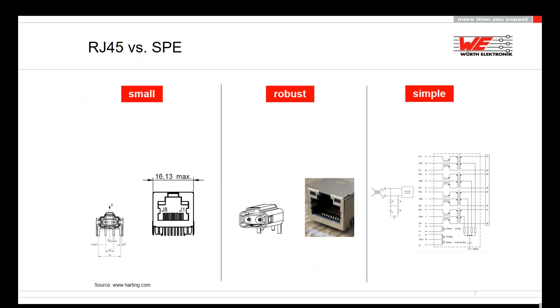What is the difference between single-pair Ethernet and RJ45, the multi-pair Ethernet? First, the SPE connector is quite smaller than the normal RJ45 connector. Second, this single-pair Ethernet connector is more robust than an RJ45, because the RJ45 has pins only at the bottom side — it is basically made for office applications, not industry. The SPE connector is designed so that when you plug it in, the contacts are fully surrounded by pins. So no matter if you pull on the cable or bend it, you always have a good contact.